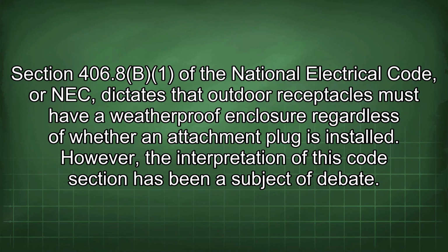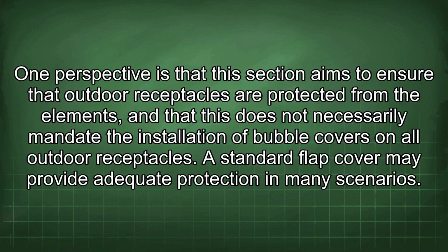Section 406.8 of the National Electrical Code, or NEC, dictates that outdoor receptacles must have a weatherproof enclosure regardless of whether an attachment plug is installed. However, the interpretation of this code section has been a subject of debate. One perspective is that this section aims to ensure that outdoor receptacles are protected from the elements, and that this does not necessarily mandate the installation of bubble covers on all outdoor receptacles. A standard flap cover may provide adequate protection in many scenarios.